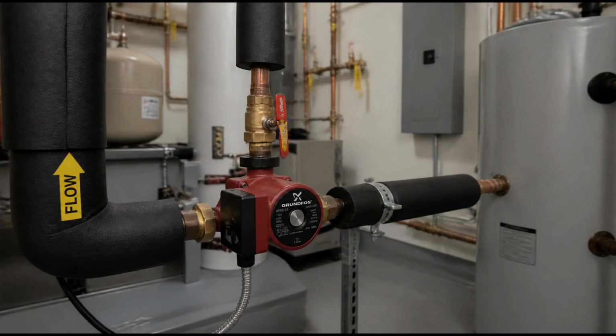Throughout the recirculation loop, check valves ensure that water moves in the correct direction. These are one-way valves. They open freely to let water flow in the intended direction and close automatically if flow reverses. In a loop system with multiple branches, proper placement of check valves is essential to prevent short-circuiting, where water takes the path of least resistance and bypasses parts of the loop, leaving those areas without adequate circulation.